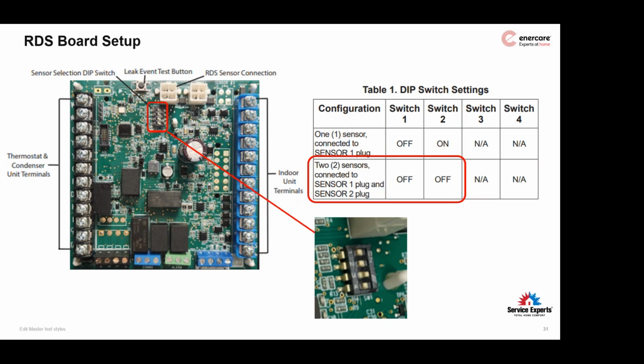If you're only connected to one A2L sensor on the control, switch number 2, which is right here, there's going to be a little arrow coming up. Yeah, switch number 2 must be moved to the on position, or pushed over to the right. We'll go into the furnace one in a second. Using the RDS board pictured, push the switch to the right side. On the furnace boards, the switch will be pushed up instead of right, in the upflow furnaces.